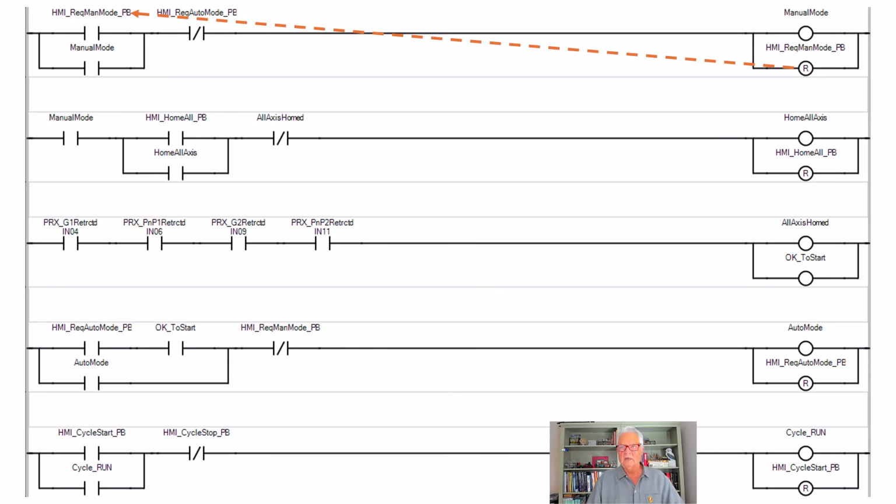By the way, reset and unlatch are the same thing. Latch, unlatch goes back to the 2-coil latching relay of yesteryear. 1 coil closed the contacts and they were mechanically latched. The other coil releases the mechanical latch and lets it return. In computerese, they typically say set and reset instead.